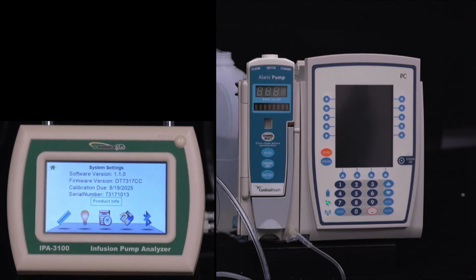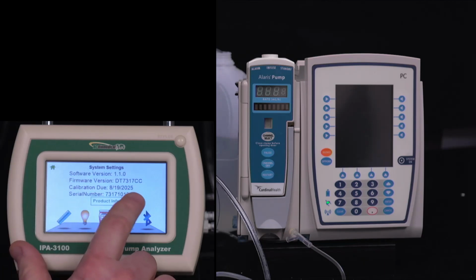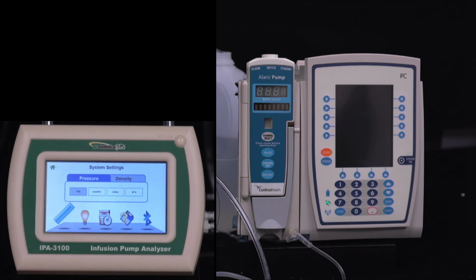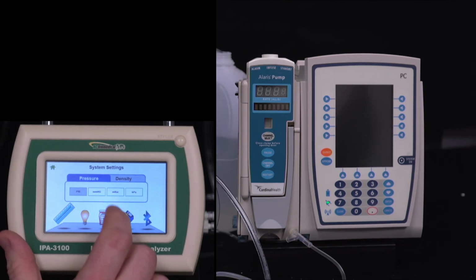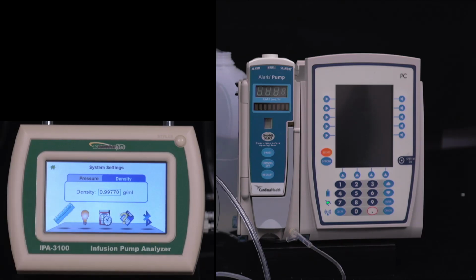And then we have the settings over here. So the settings allow us to see when the unit is due for calibration, serial number, software, that sort of thing. And then we can change the pressure units if we don't want PSI. Maybe we have a device that wants millimeters of mercury or some other unit of measure. And then we also have a setting for density. Now, this is going to come in handy when we're testing the Alaris pump because I'm sure you're familiar with that procedure. They want grams. They want you to use a scale. But a scale can be a little clumsy when doing infusion testing, and also we can not only do the grams measurement with the IPA, we can also do the pressure measurement for the occlusion. But this density setting allows us to convert our measured milliliters into grams for PM procedures like the Alaris.